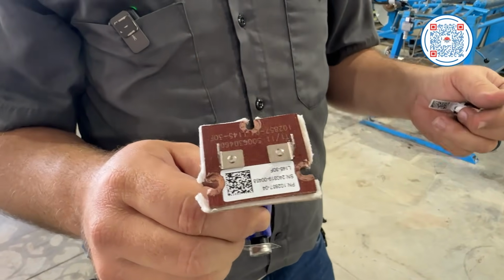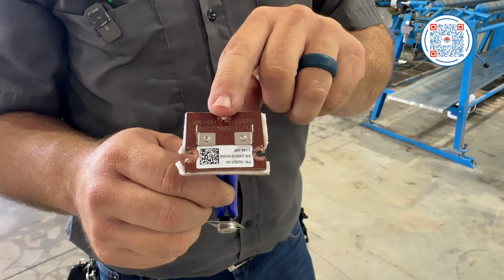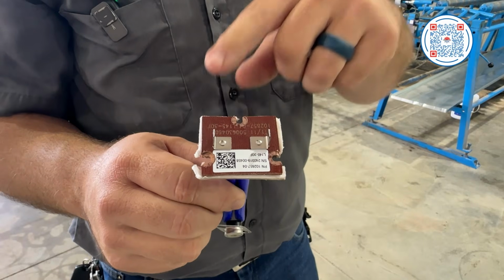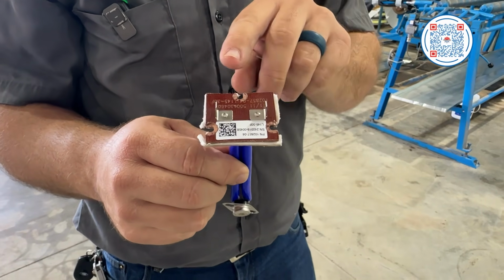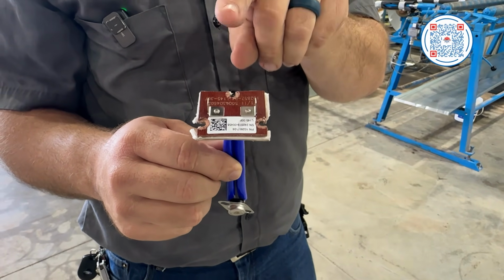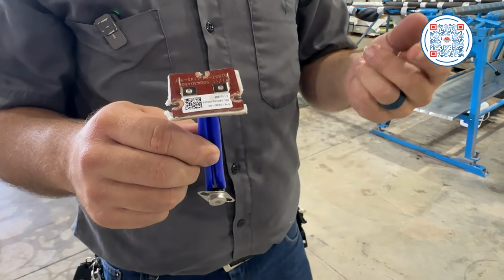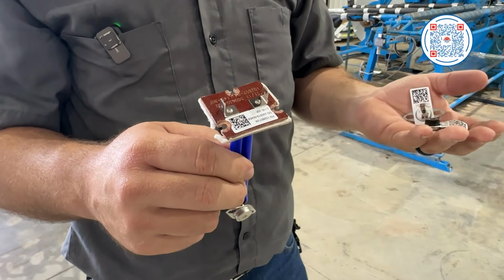This is actually a high limit, and this limit resets. So if your heat gets too high, it'll kick it off, run the fan for a while so it cools down that heat exchanger, and then it'll allow you to go back to business once it reaches its points.